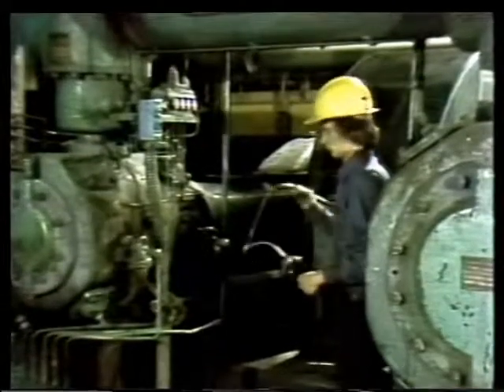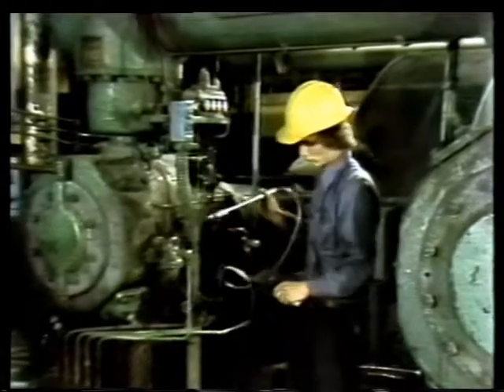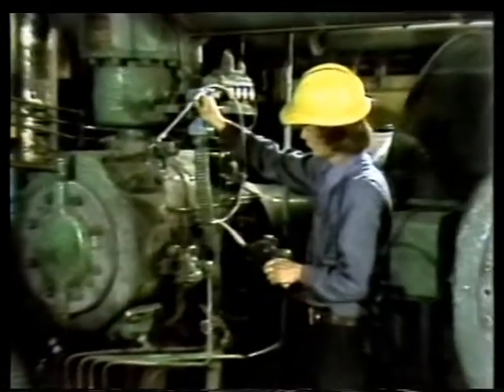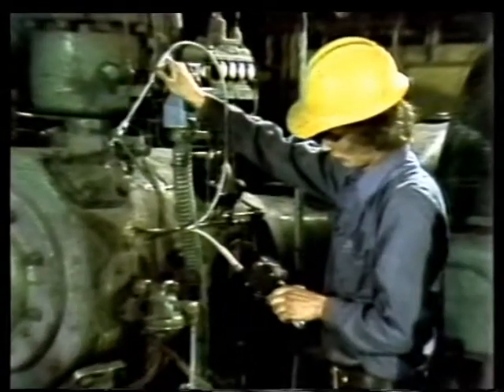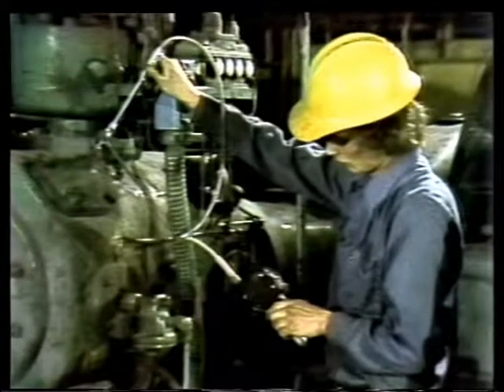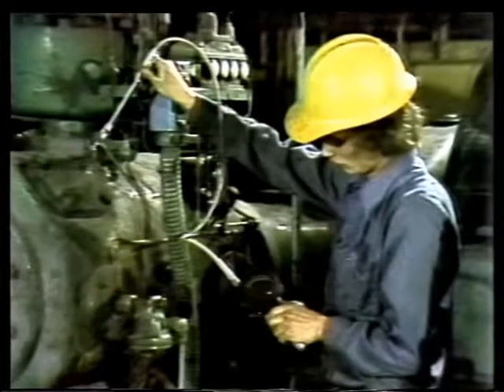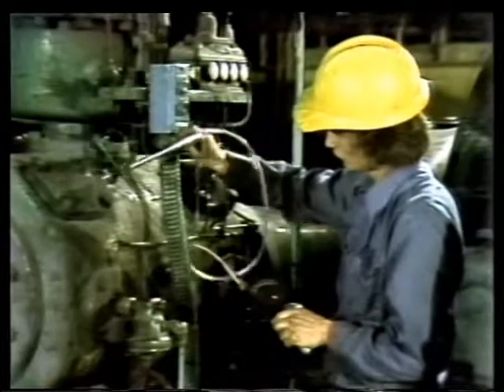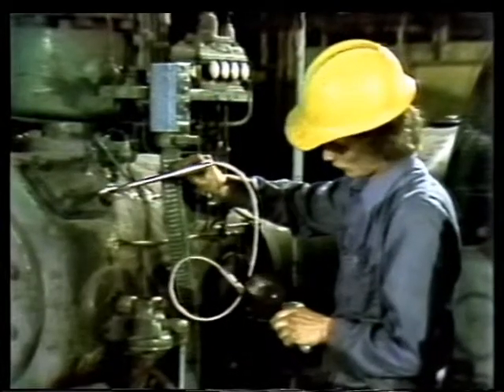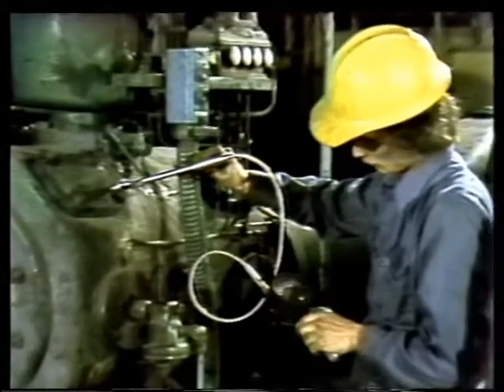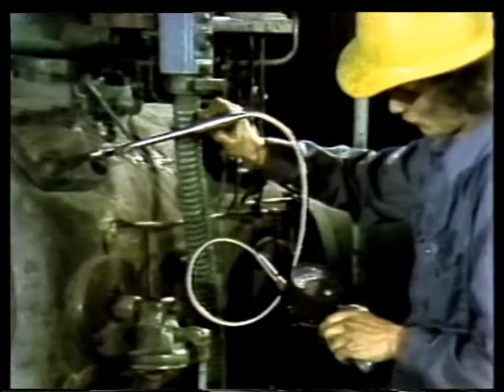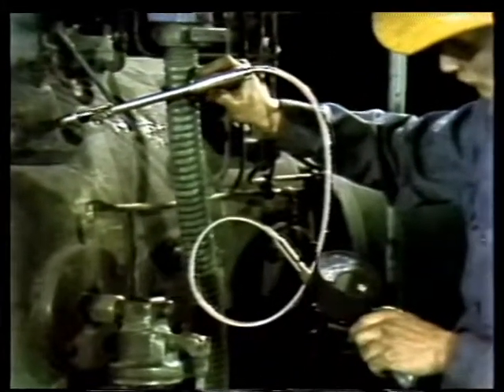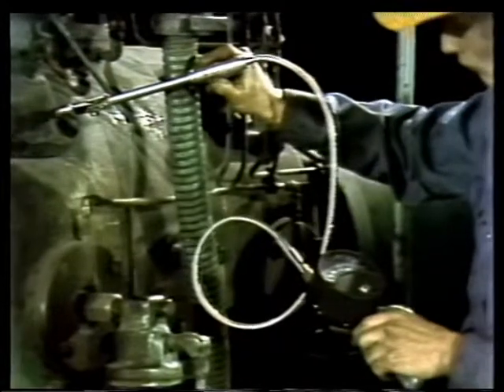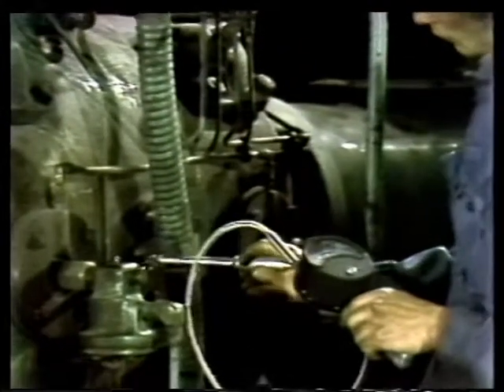After pinpointing the noise, you should check for other symptoms. If the knock is in the cylinder, the problem could be a valve, a loose piston, or piston rod, no lube oil, or a cylinder or piston that is worn or scored. If the knocking sound is caused by a valve, the valve would be hotter than normal. The valve could be loose and banging against the cylinder, causing friction. This friction could be the source of excess heat in the valve.